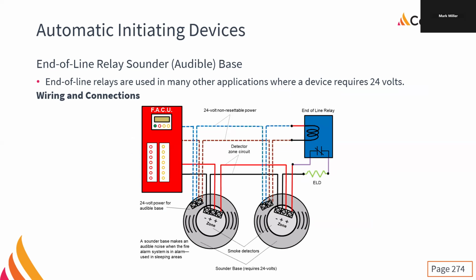There are other times that we use the non-resettable. If we need 24 volts to power things like sounder bases. They're also referred to as audible bases. A sounder base makes the noise when the fire alarm system is in alarm. We use these in sleeping areas instead of using smoke alarms. If we use a smoke detector with a sounder base, when that detector activates, it's going to make the noise exactly like a smoke alarm does. So if we install these, we don't have to install smoke alarms.